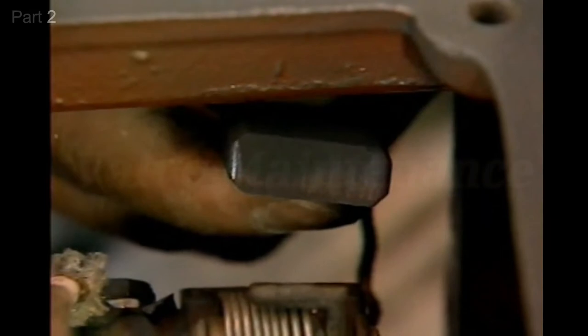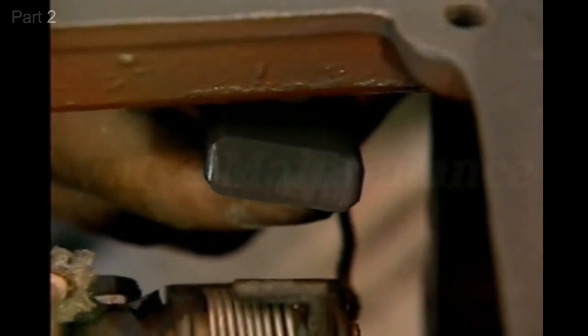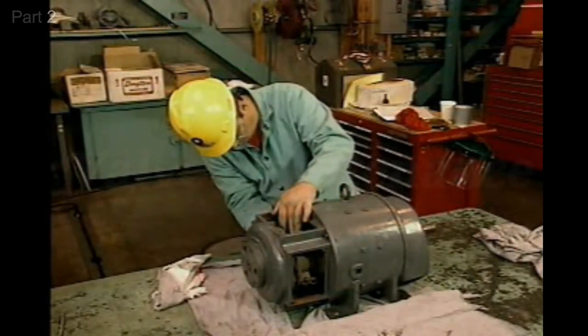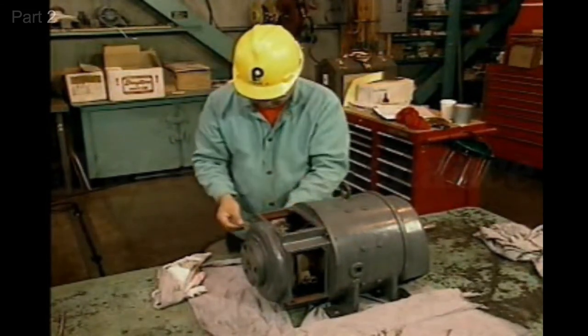If it doesn't, the procedure with the flint paper is repeated. When the shape of all of the brushes conforms to the shape of the commutator, the seating procedure is complete.